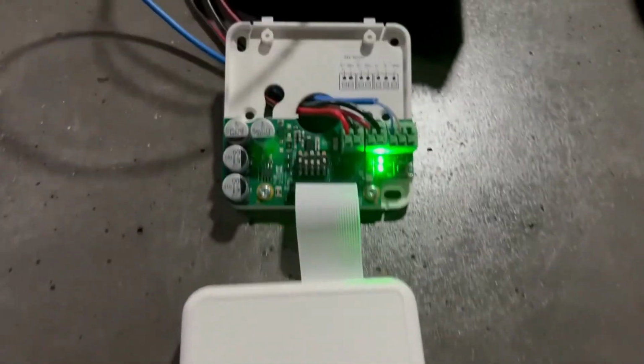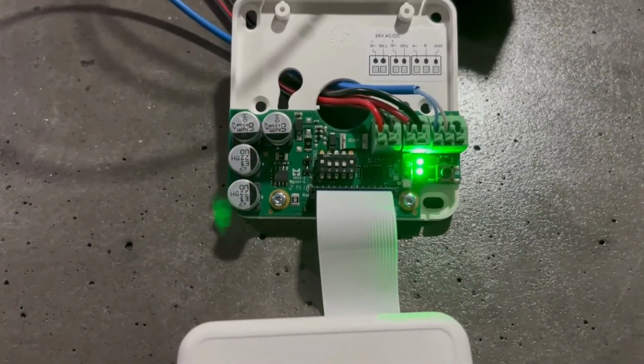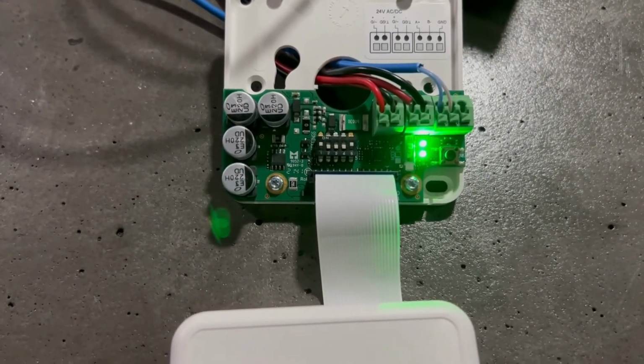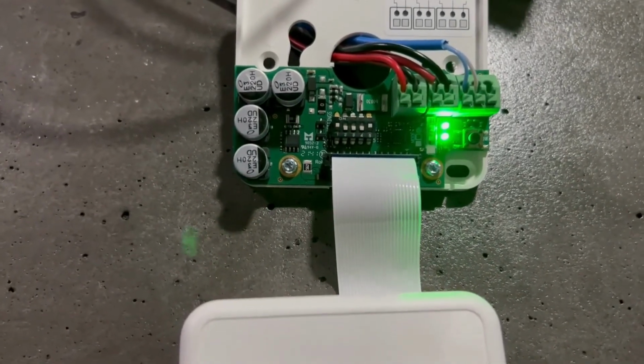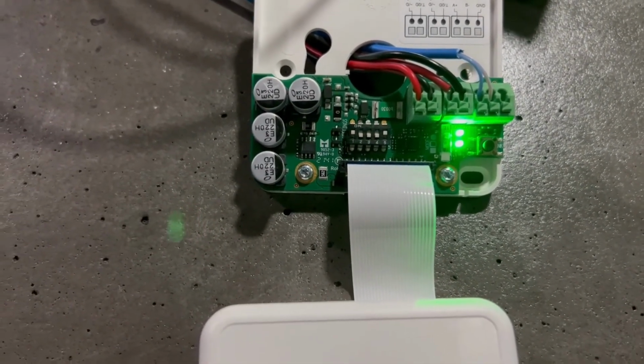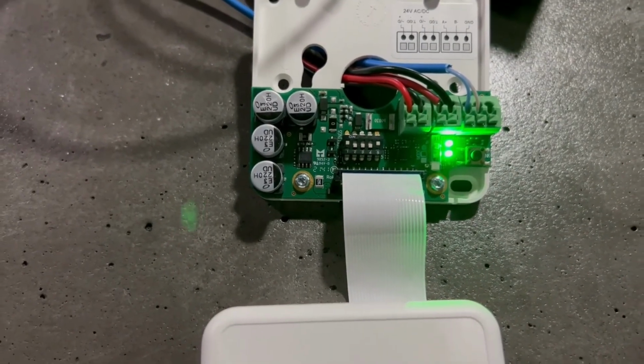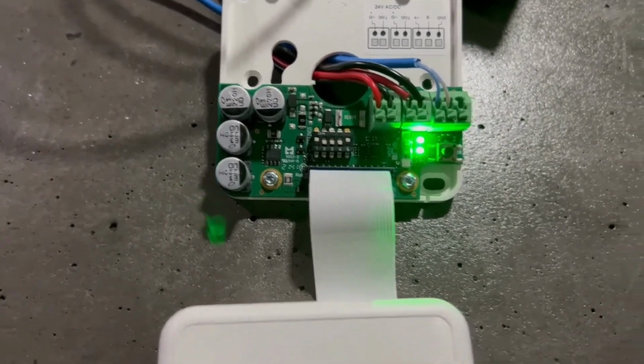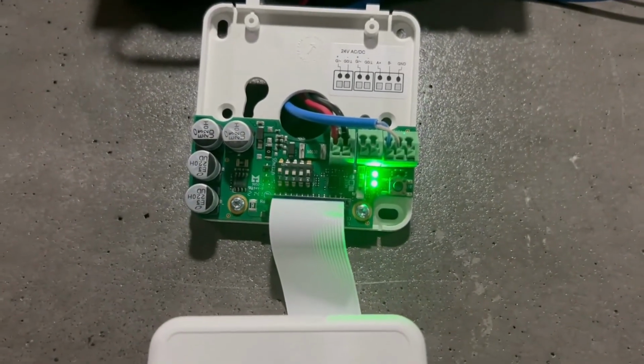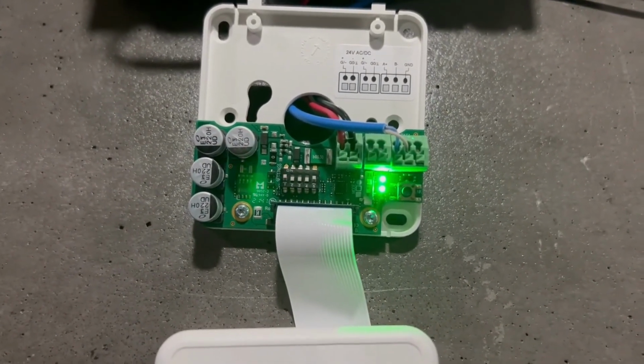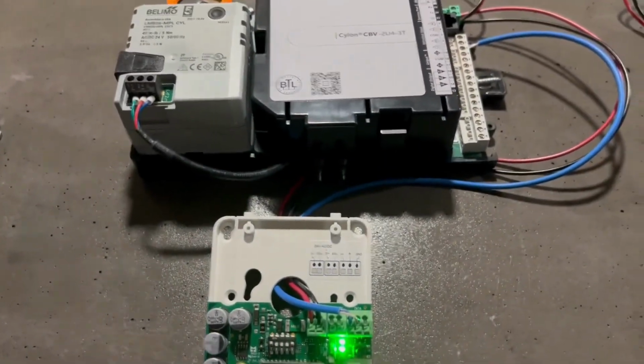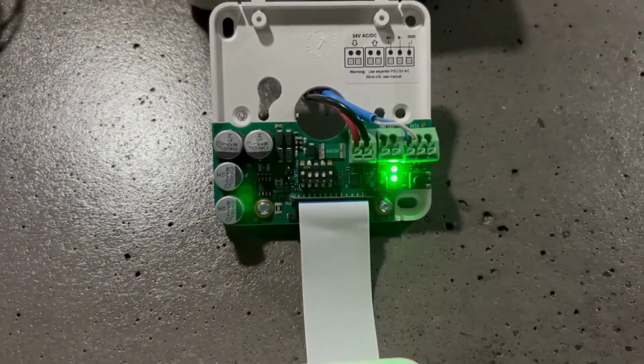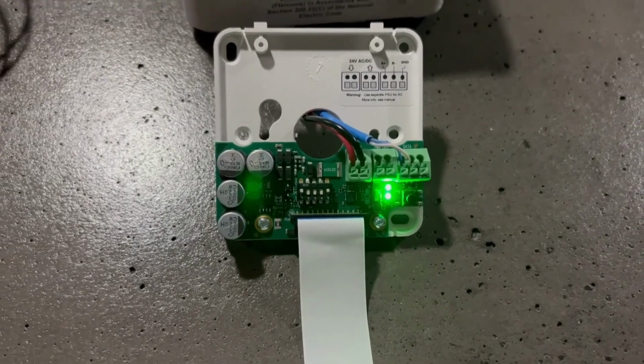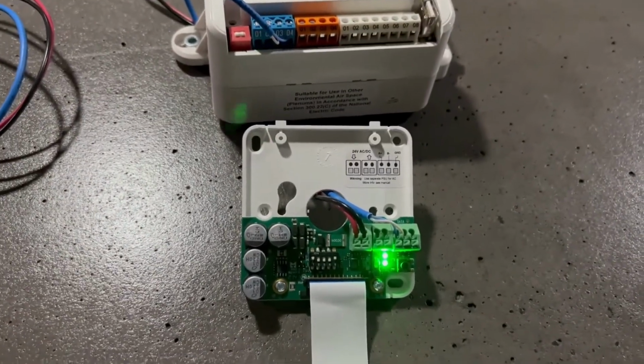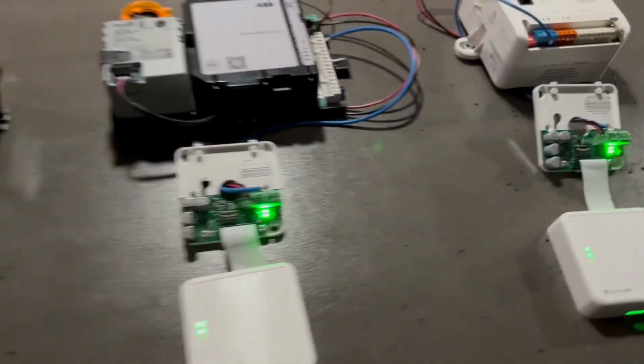And you'll see here, this one is finally set up. You've got the middle green, meaning it's a good signal. Obviously, these are only a foot apart. And then the bottom LED will blink green if it's communicating MSTP, which it is. So that's set up and working properly. We go to the second one. This LED sequence is correct and communicating properly with the device. And the same with the third device. It's all set up and functioning. So now we have a mesh of three nodes and a gateway.